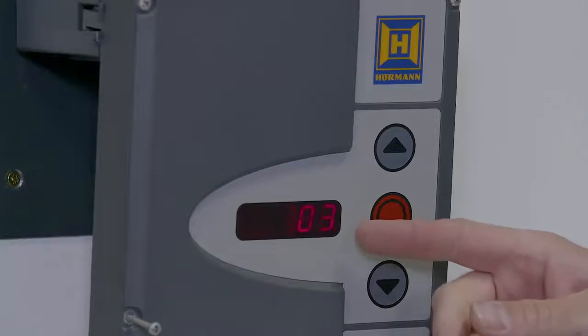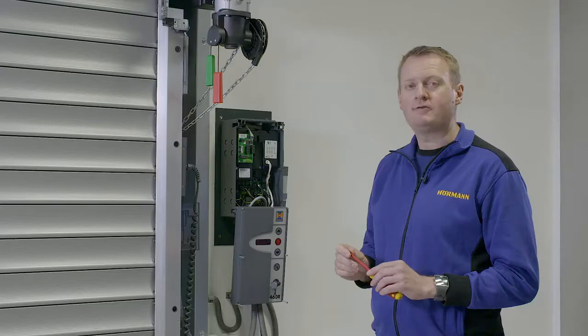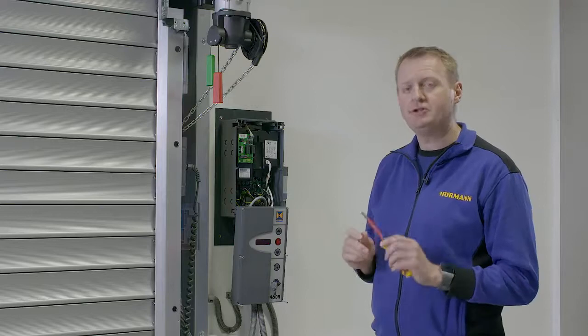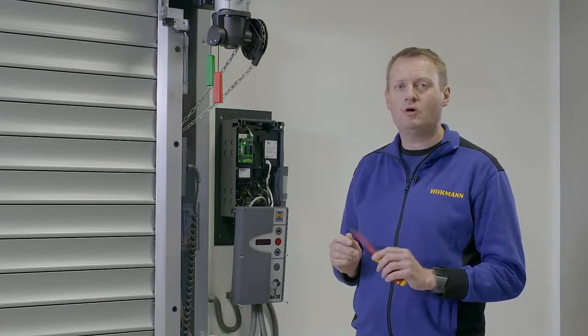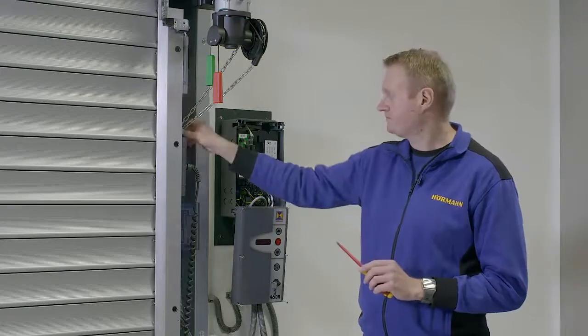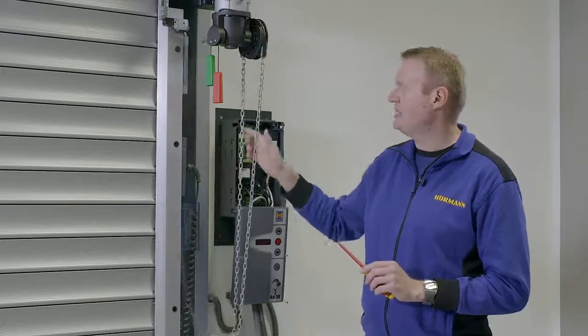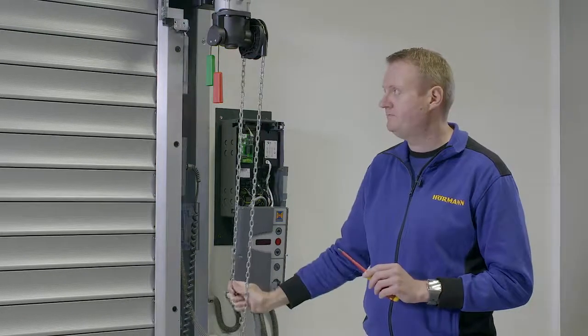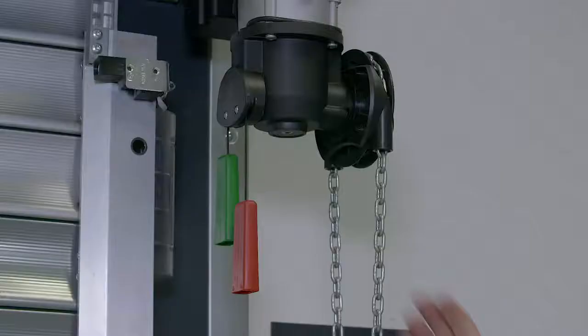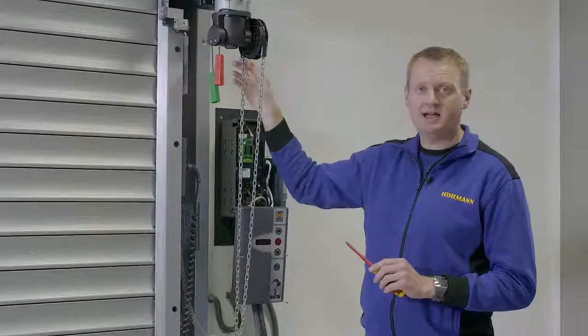Error code 03 is the signal for the safety switches for the manual override of the motor. There are two types of manual override on the motor: either the hand chain or a winding handle. For a hand chain, see if the door will raise using the chain. If it does, pull the green toggle and disengage the chain.